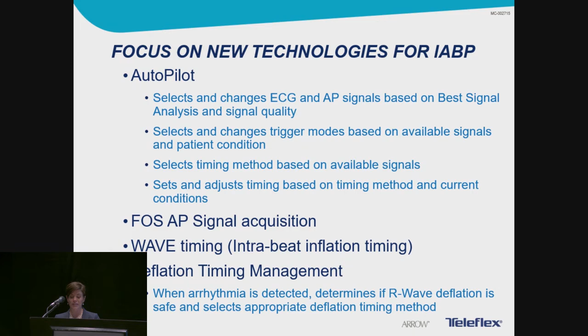The first PV loops show, you can see it's the taller, skinnier, and I apologize, the video on this slide is not working. So the first PV loop shows the impact of the balloon pump on LV function with optimal support, meaning proper timing, full volume, and one-to-one assist. Now, this shows the effect of the balloon pump is immediate within the first 3 to 4 beats. So the change that you're looking at is going to change that PV loop to shorter and wider. That's going to show us that decrease in pressure and an increase in stroke volume. So we're moving more volume easier.